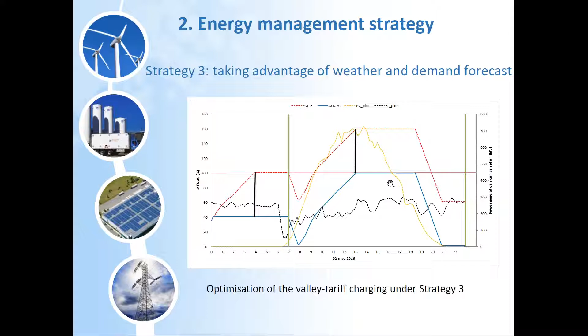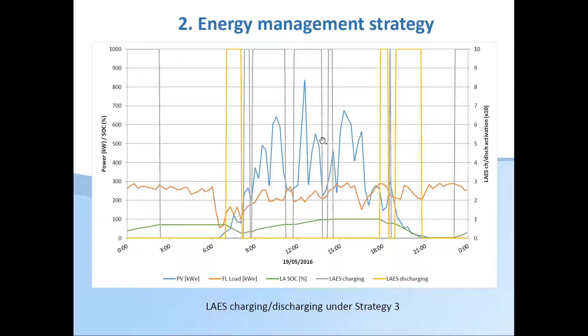This is another example of the same performance. The gray boxes show the system charging, and the orange ones show when the system is discharging. So in this case, we charge the system a little during the night, up to about 60% state of charge. Then during the morning, we discharge the system a bit to get storage capacity for charging all the surplus renewables during the day. You can see there are several start and stops during the day, which we should minimize since this system doesn't have a fast start and stop, and frequent cycling isn't good for the equipment in general. So we should try to minimize this and include it in the optimization.